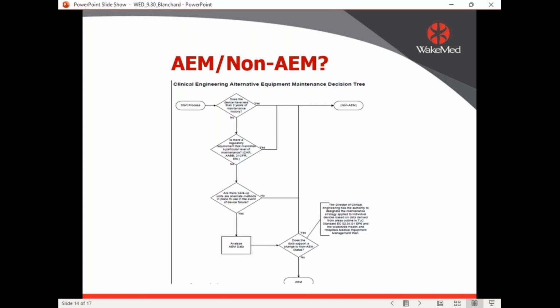If it doesn't fall into that, are there backup units or alternate methods in place to be used in the event of device failure? So why does that determine whether something should be AEM or non-AEM? If you have a ton of backups, that helps support maybe pulling something out of your AEM, or putting it on an AEM program. You can let it run to fail instead of having to do PMs on it. So we decided that that's a factor.